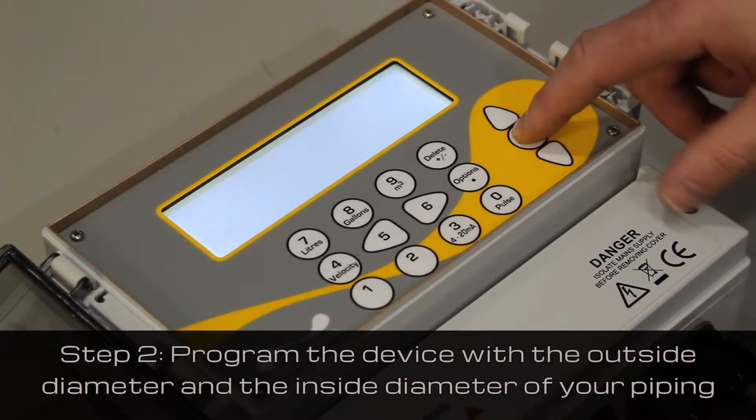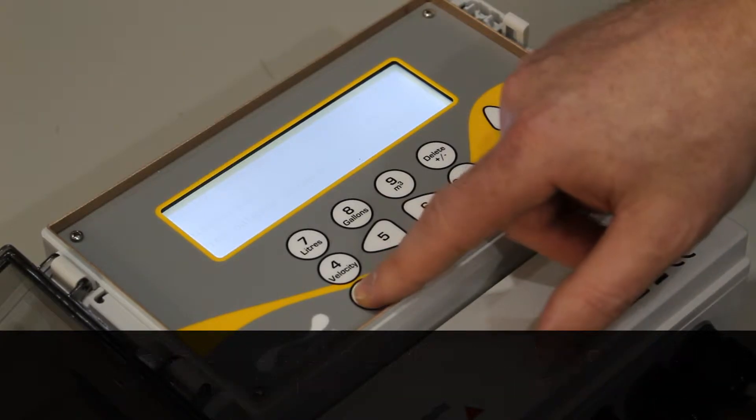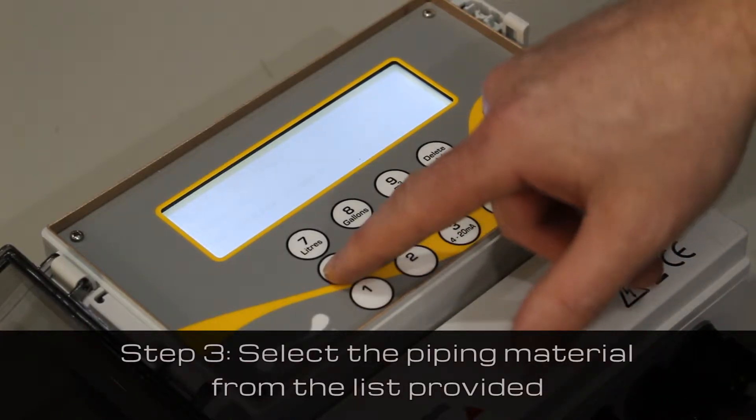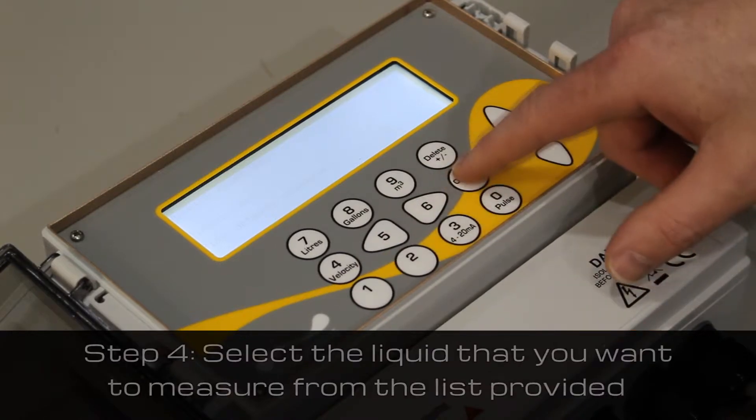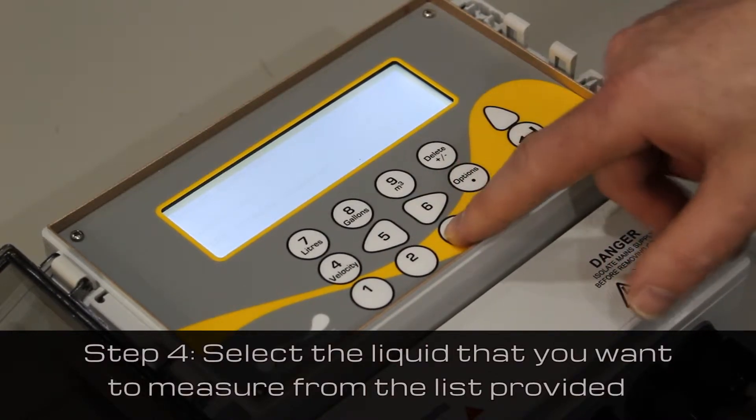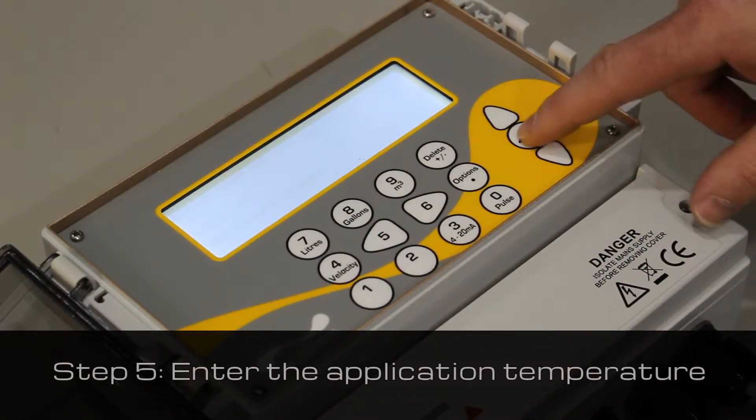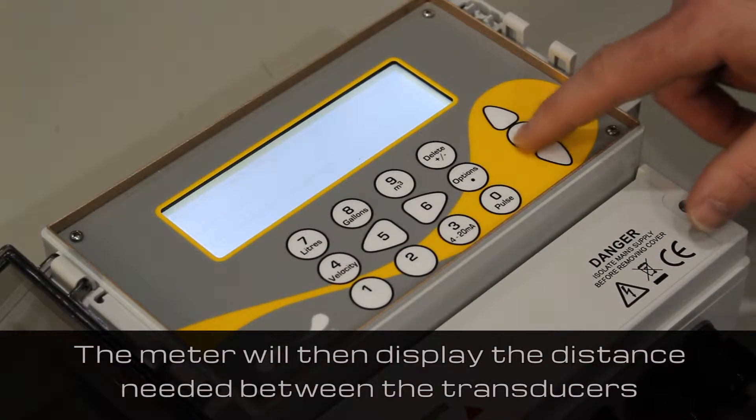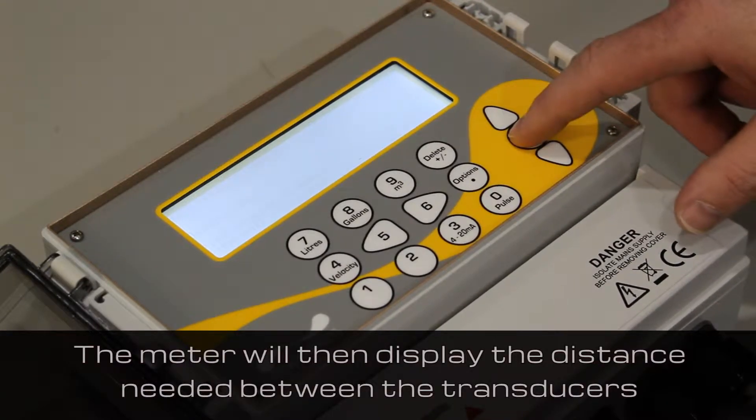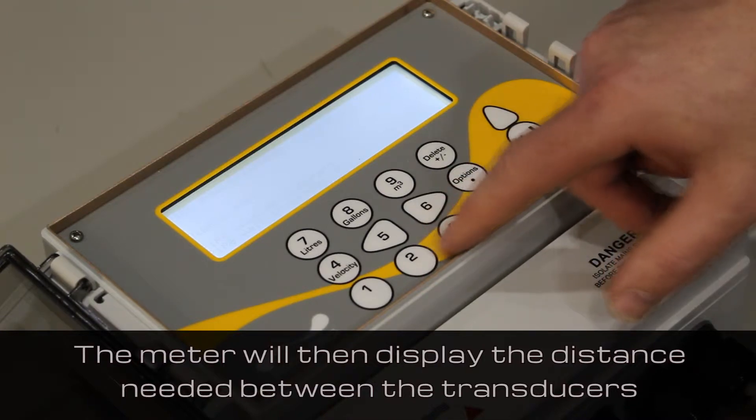You will need to program the device with the outside diameter and the inside diameter of your piping. Then select the piping material from the list provided. Next, select the liquid that you want to measure from the list provided. Enter the application temperature. The meter will then calculate the distance needed between the transducers and will display it on the screen.